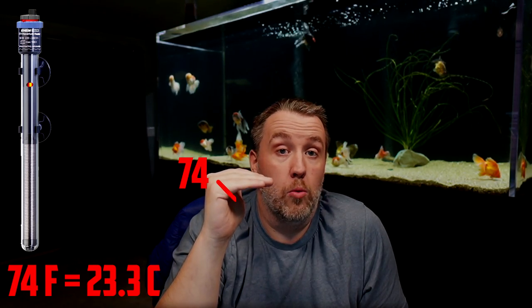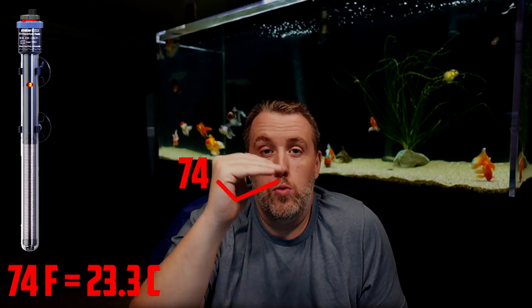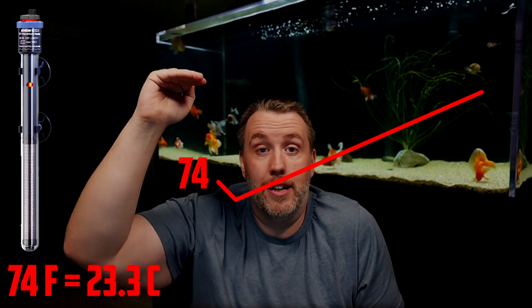Optimally, we might sit at 74. It goes dink, 73, and we're a little bit under where we want to be. Let's turn this heater on. And then over the course of 4 or 5 hours, we hit 78, turn off. And then maybe it does that once more per day, right? Maybe it's doing that once every 12 hours. Whereas with something like this right now, we've got it set at 78. The minute it goes to 77.8, boom, it's going to kick back on. And it's going to be on and offing 50 times, 100 times a day.